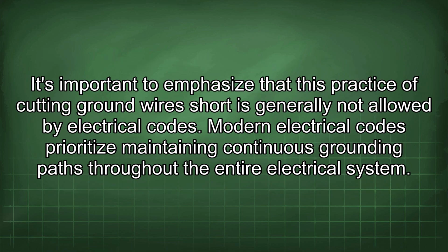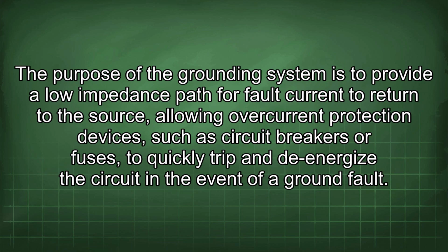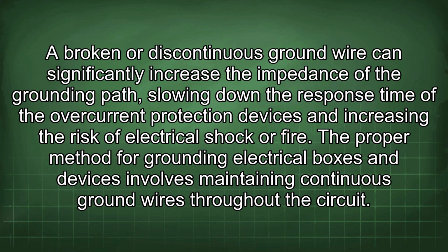It's important to emphasize that this practice of cutting ground wires short is generally not allowed by electrical codes. Modern electrical codes prioritize maintaining continuous grounding paths throughout the entire electrical system. The purpose of the grounding system is to provide a low impedance path for fault current to return to the source, allowing overcurrent protection devices, such as circuit breakers or fuses, to quickly trip and de-energize the circuit in the event of a ground fault. A broken or discontinuous ground wire can significantly increase the impedance of the grounding path, slowing down the response time of the overcurrent protection devices and increasing the risk of electrical shock or fire.